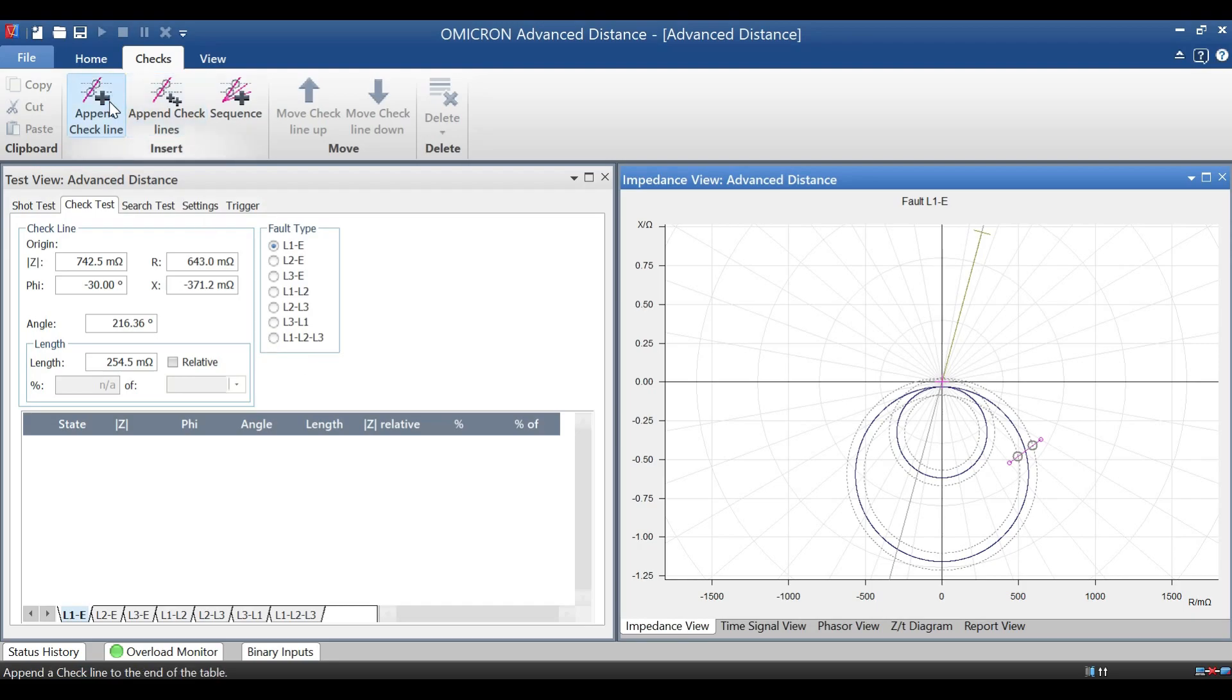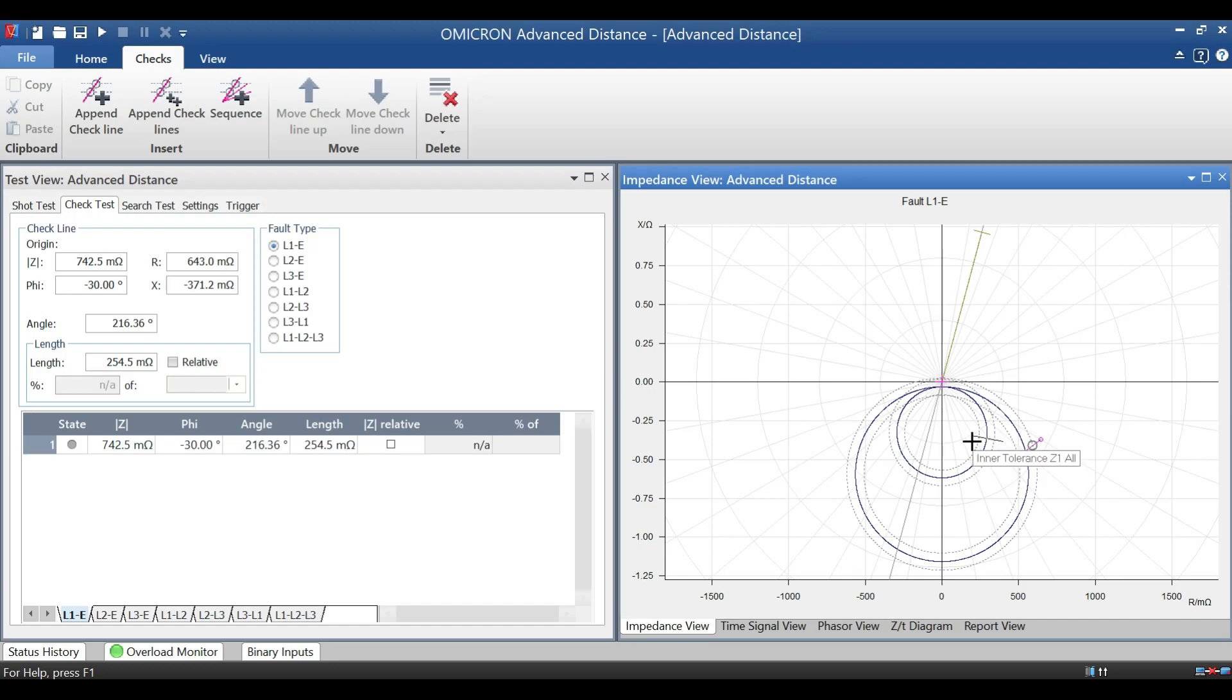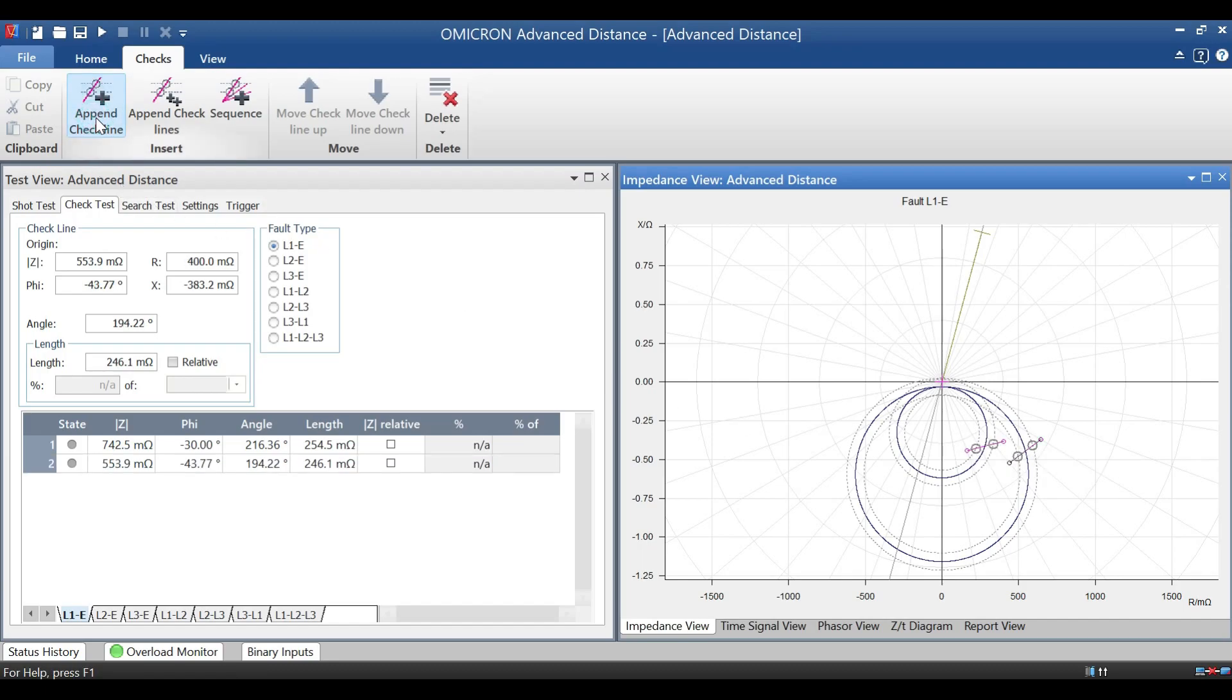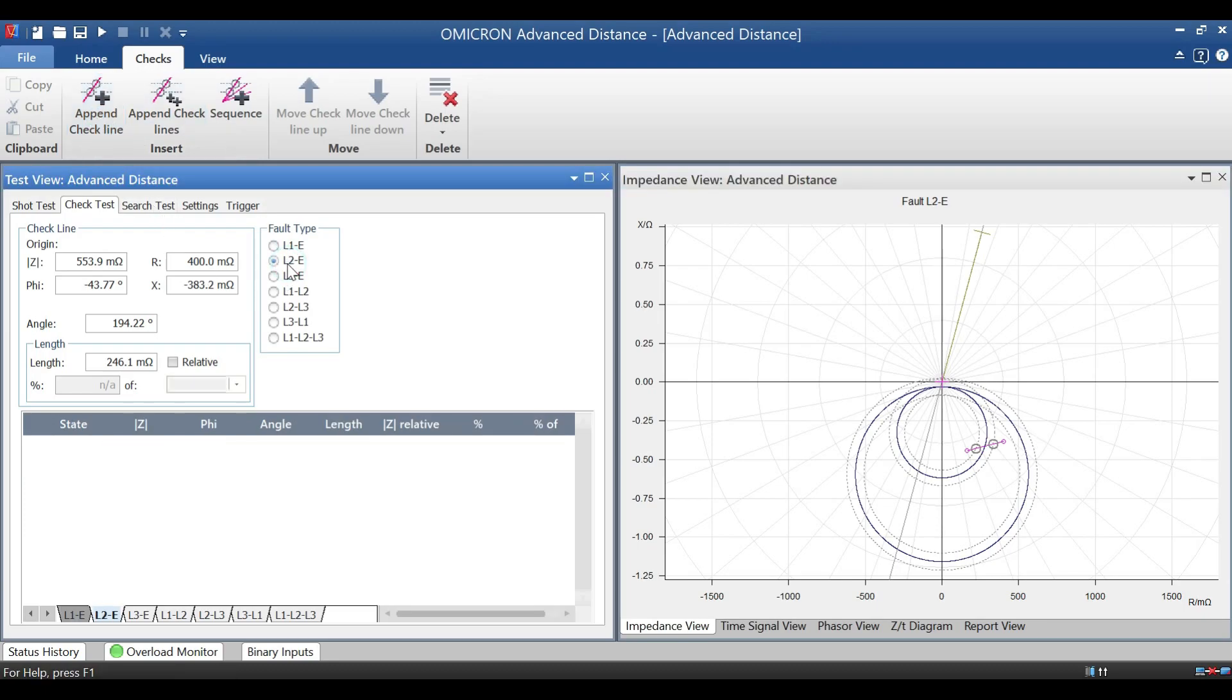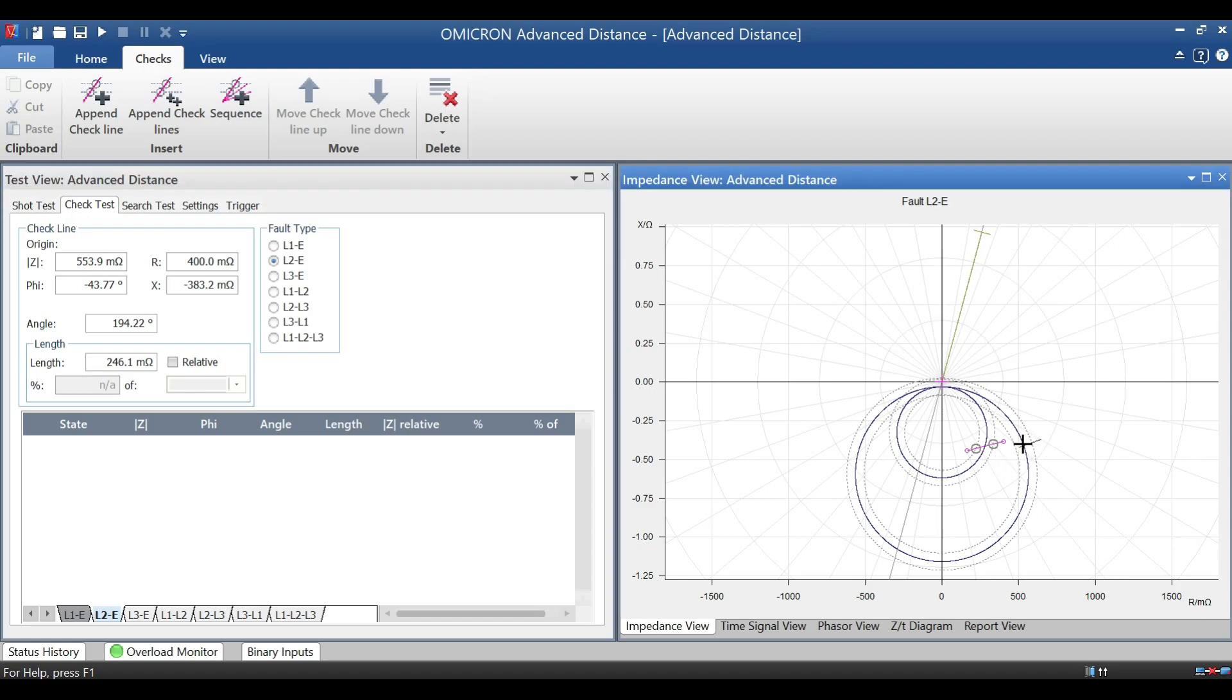But in actual case, if you do for three phase fault itself, it is OK for testing loss of field. No need for testing a single phase fault also. But if customer recommend, then you can go for testing single phase fault.